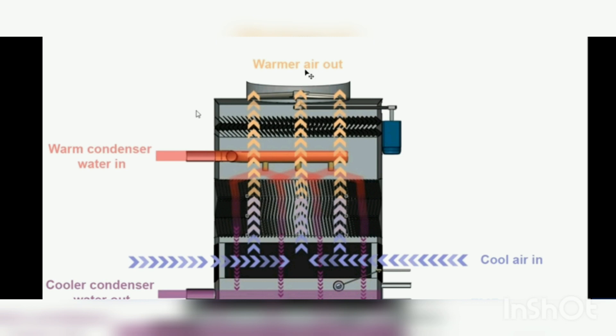The air is sucked into the cooling tower because a fan is provided at the top. As the fan runs, it pulls the air out, and to pull the air out it must first suck air in. You can see in the diagram the 'cool air in' symbol just above the bottom. This type of cooling tower is known as an induced draft cooling tower. Since the water comes down and the air comes up, it can also be called a counter flow cooling tower.